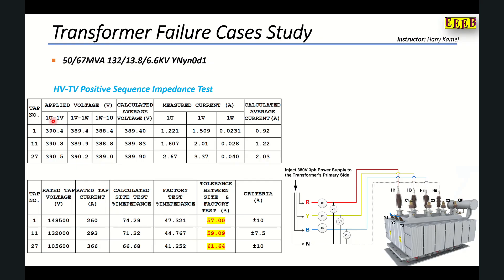We have the measurements here. Between H1 and H2 we have 390.4 V at tap 1. Then between H2 and H3, and between H3 and H1 — these are the voltages between the phases. Here is the average of these three values. We also measure the current: H1 is 1.22 A, H2 is 1.5 A, and H3 is 0.02 A, meaning there is essentially no current in H3.